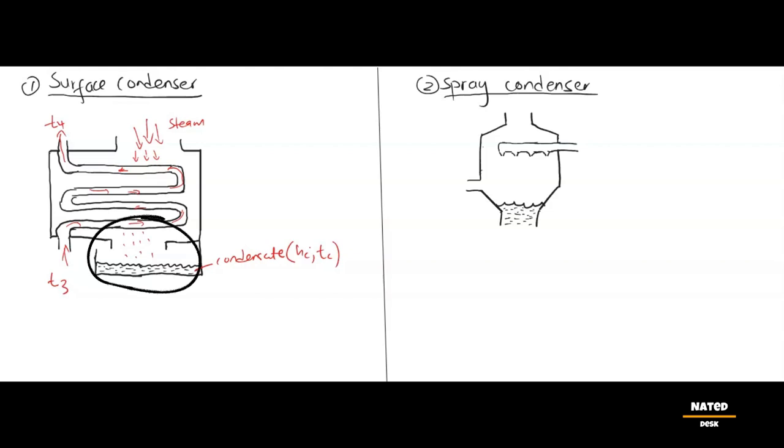5. Removal of non-condensable gases. As the steam condenses, some non-condensable gases may be present. These gases, such as air, need to be removed from the condenser to maintain the vacuum condition. Vacuum pumps or other devices are used to extract these gases and maintain the desired vacuum level. We will talk about this later in details using Dalton's law regarding partial pressure theory.